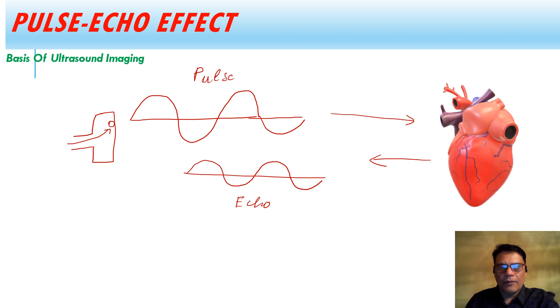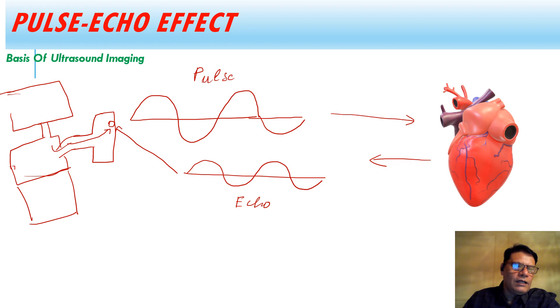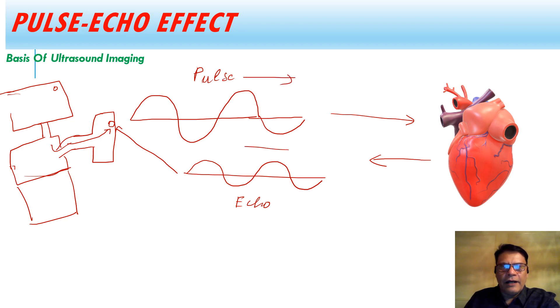It's no more a pulse — it's an echo, because it came back after reflection. This echo is received by the same piezoelectric crystal, which converts this echo into a dot on the monitor of the machine. This bright dot is the direct result of the pulse and its reflection. So this is called the pulse echo technique, which results in the formation of a bright dot.